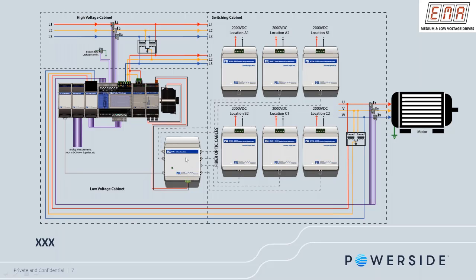We have our fiber optic interface module that isolates the medium voltage to the low voltage section. So all of these are on our low voltage section, as you can see. And then on our medium voltage section, we have MVM modules that can take up to 2000 volts DC. So we can tie each of these to a power module on a VFD. For example, on a Toshiba VFD, we have 6 DC buses on a 4160 volt system, right?